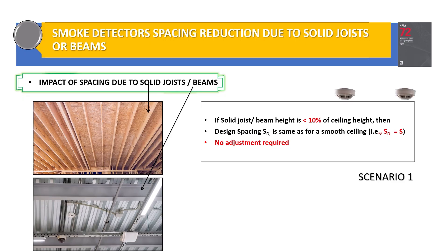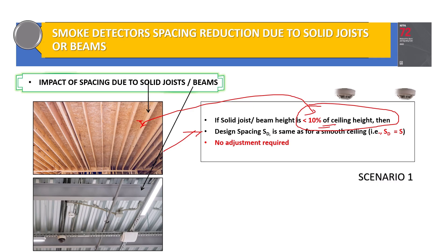Let us discuss Scenario 1. Look at the screen — we have figures showing solid joists and beams. If your building has either solid joists or beams, Scenario 1 applies when the solid joists have a depth less than 10 percent of the ceiling height, or if you have beams in your project that are also less than 10 percent of the ceiling height.